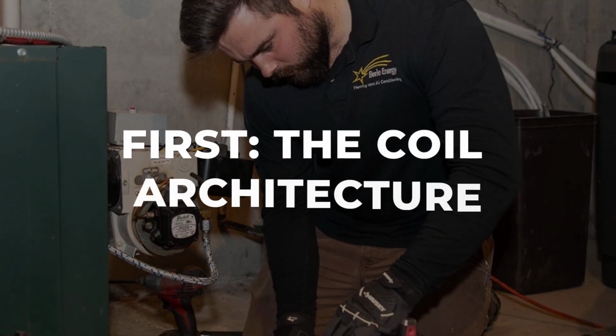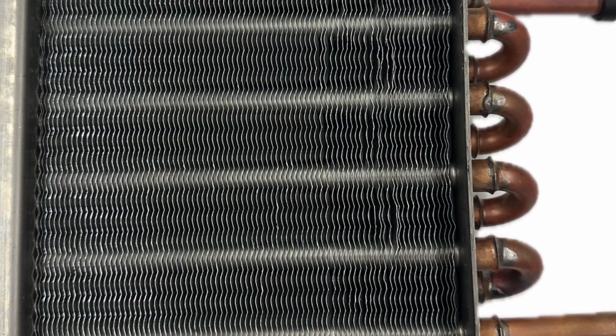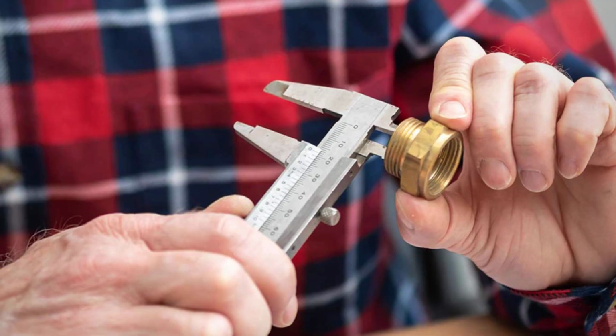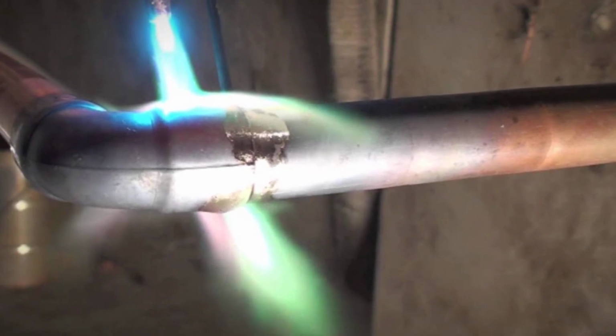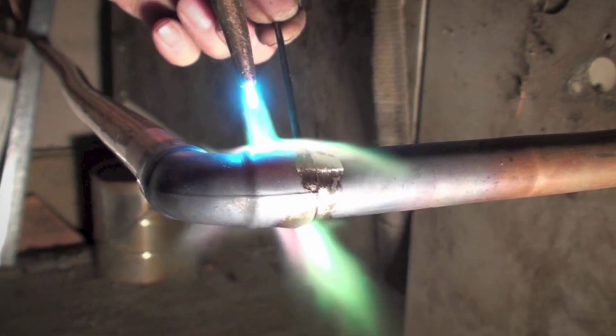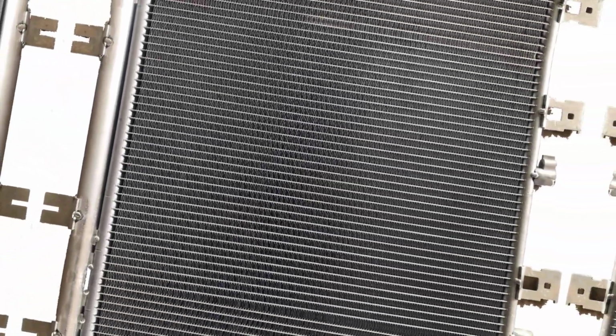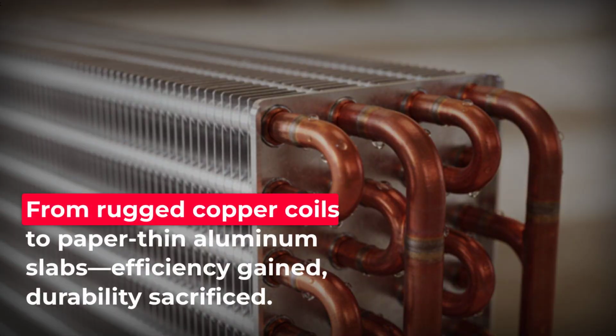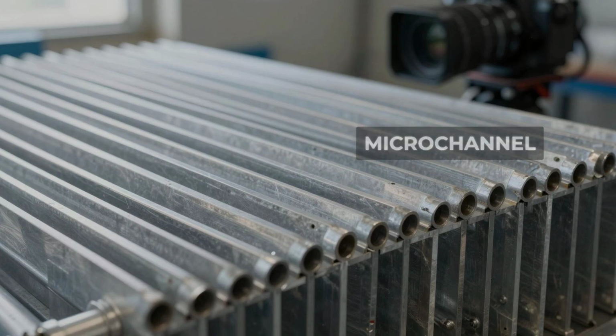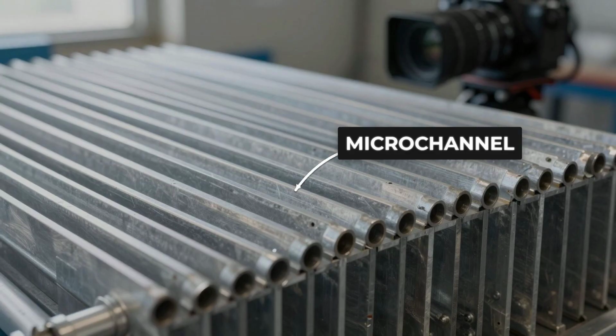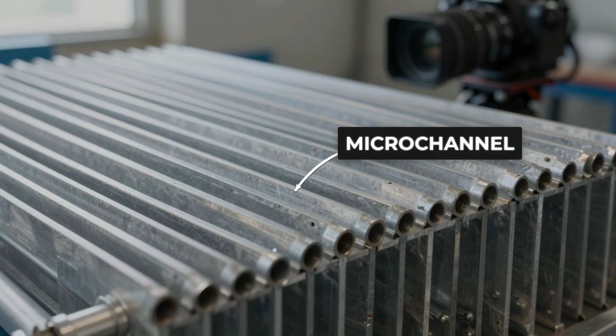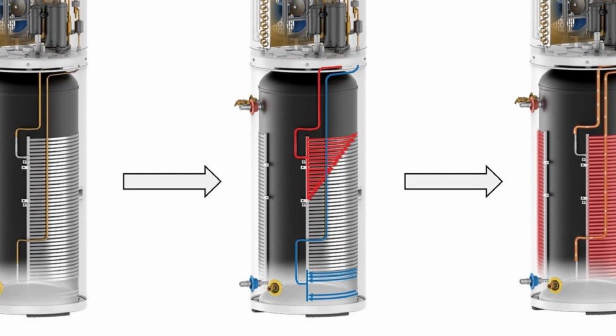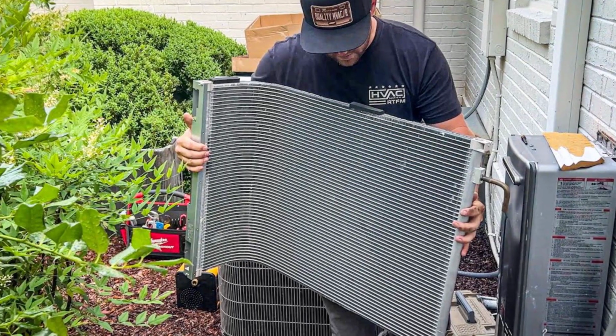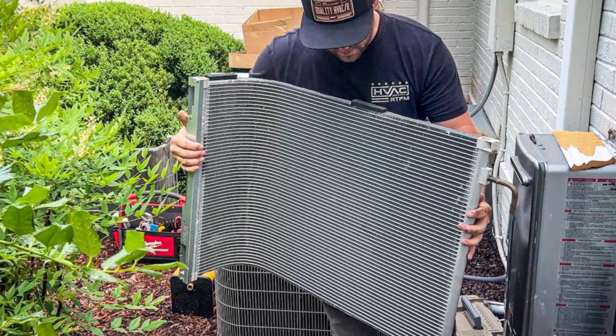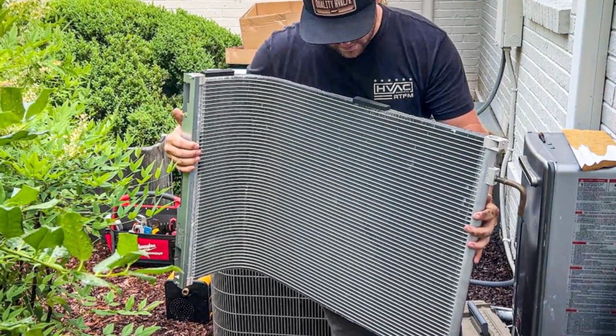First, the coil architecture. Older heat pumps used conventional round copper tubes running through aluminum fin blocks. The tubes had enough wall thickness to handle decades of thermal cycling and enough diameter to tolerate a minor field repair. What changed? Manufacturers borrowed all-aluminum microchannel technology from automotive radiators. Trane's own service literature describes microchannel as flat, multi-port aluminum tubes with extremely high surface area density packed into a compact slab. It transfers heat beautifully on a test bench. It also creates passages so tight and walls so thin that damage which once meant a localized braze job now means an OEM part replacement.